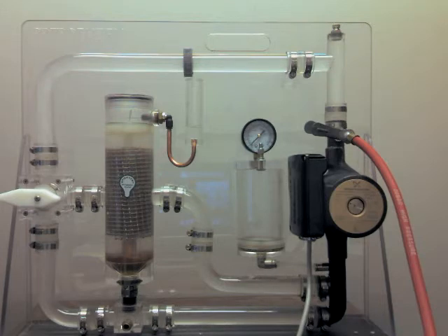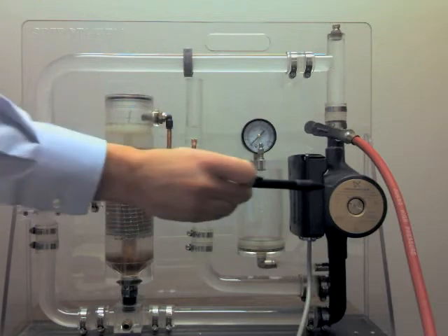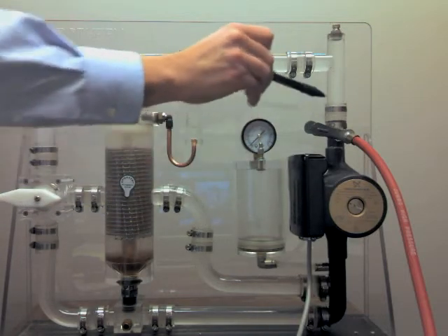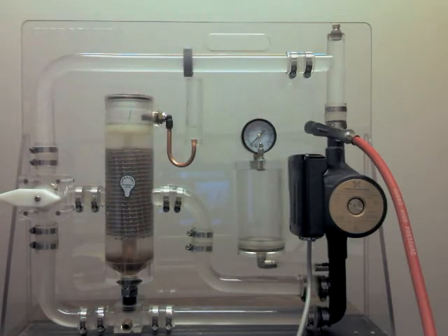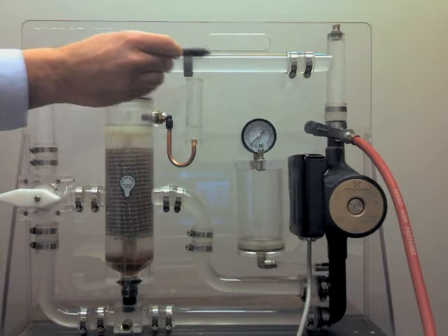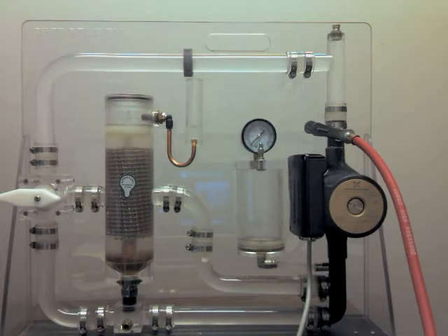And then, getting back to equipment and energy, there's a lot of wire to water energy being wasted right now with this pump, because what's happening is it's trying to squeeze those air bubbles. Air is compressible, water is not, and it's referring back to that slide I showed you in the beginning about how just a couple percentages of entrained air can reduce the pump efficiencies.